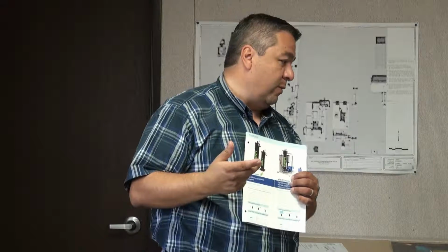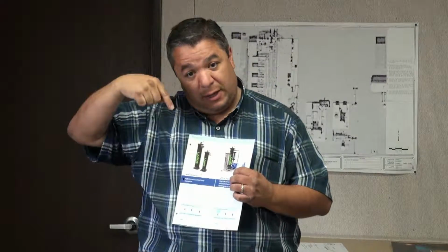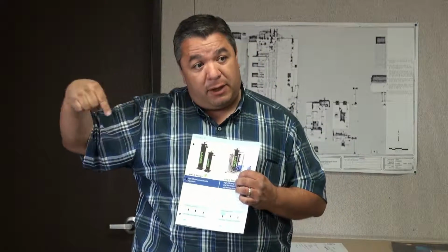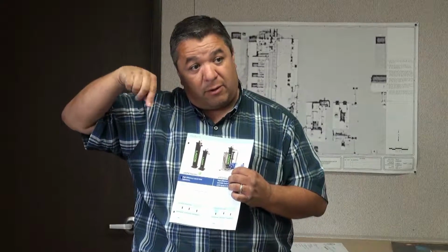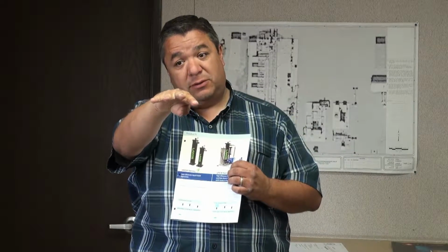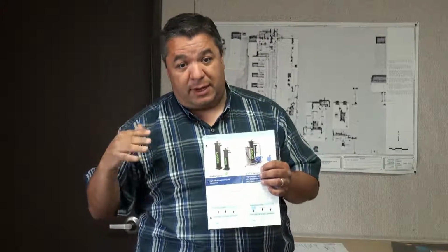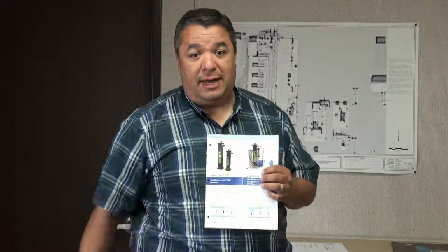Because if we installed them, and I'm sure you've seen them on this tower, it's PVC piping. It goes all along the perimeters of the tower with nozzles, high flow nozzles that are pushing everything out of the basin and into the return of the Lakos.